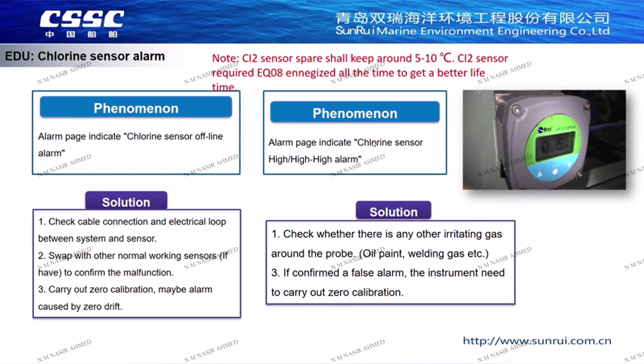If a detection high alarm is triggered, first confirm whether there is welding or painting work nearby. This volatile gas will also be detected by the sensor and trigger a high alarm. If it is caused by zero drift, zero calibration is required.